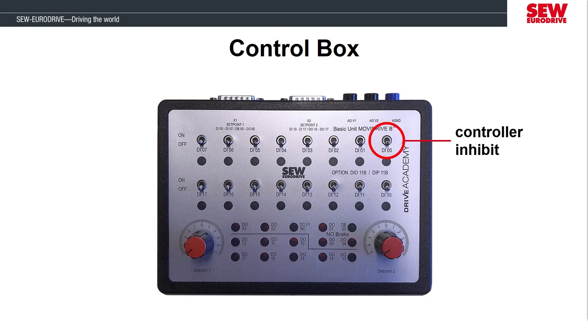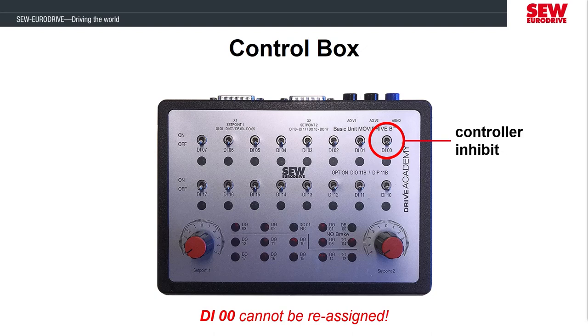The MOVIDRIVE that I'm demoing is not connected to a higher level PLC, so I will be controlling it via its terminals using a digital input and output switchbox. The MOVIDRIVE won't operate the motor without being cleared from an inhibit state. DI00 is a permanent input on the MOVIDRIVE and it can't be reassigned, so in later lab exercises this input will need to remain switched on to be clear from the inhibit.